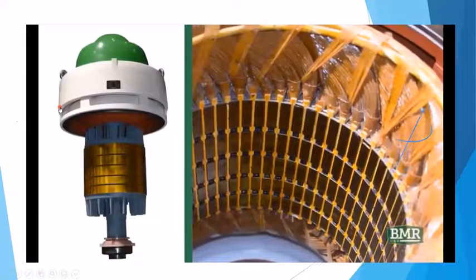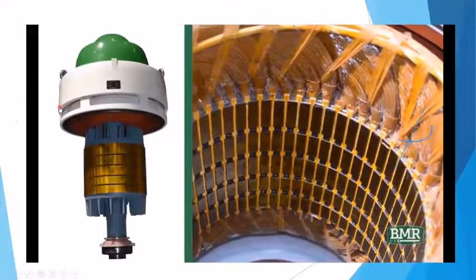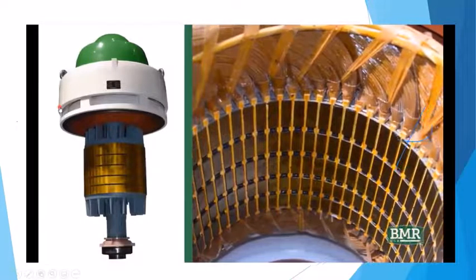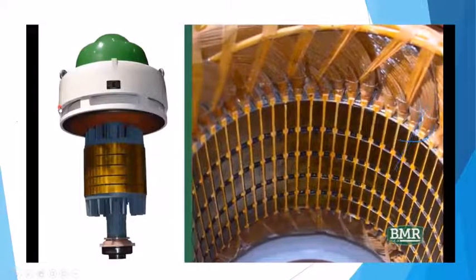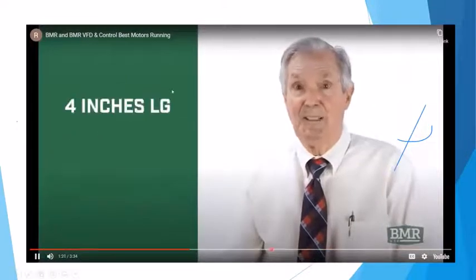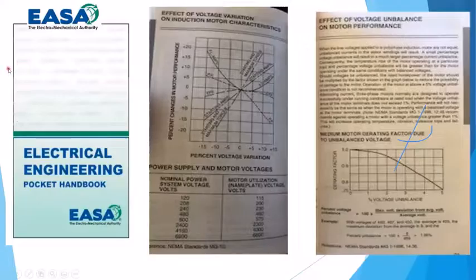Along with several best design features, electrical cores were ventilated to provide the lowest thermal hotspot. This allowed us to provide a product offering of 300 to 600 horsepower with Class B temperatures at 1.15 service factor in 50 degrees C ambient, presuming NEMA normal service conditions. The next increase in offering will continue this philosophy. 4 inches in core length can be duplicated.